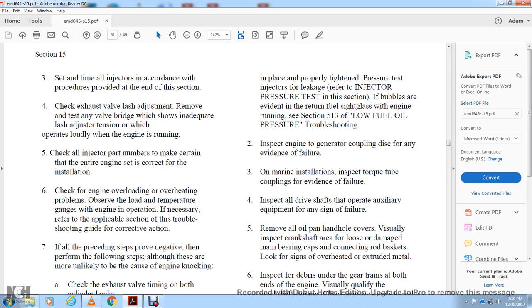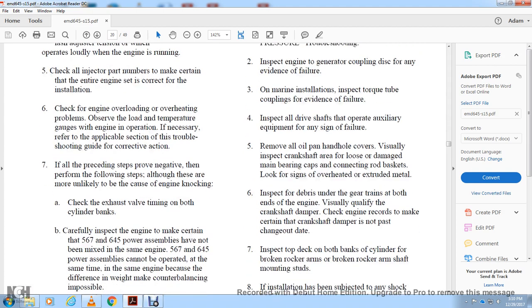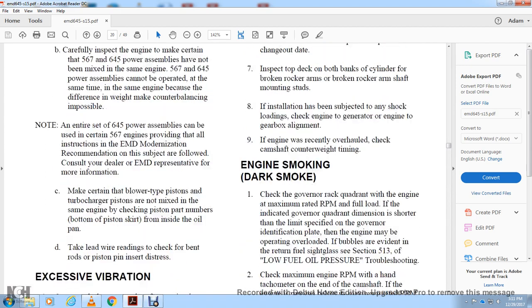Remove the oil pan handhole cover and visually inspect the crankshaft area for loose or damaged main bearing caps and connecting rod bearing locks. Look for signs of overheated or extruded metal and inspect debris in the gear trains. Visually qualify the crankshaft damper. Check cylinders, rocker arms, broken arms, shaft mounting bolts, and verify the installation status. Check the engine-to-generator alignment. If the engine was recently overhauled, check the camshaft counterweight timing.